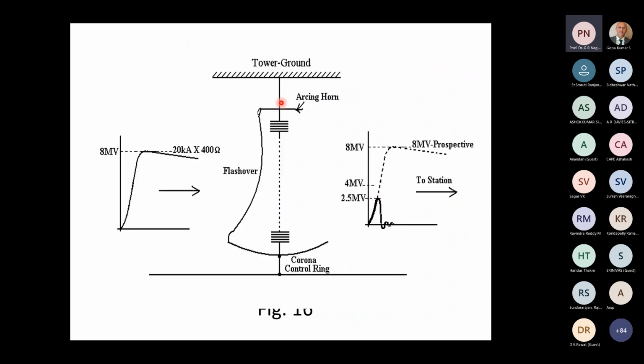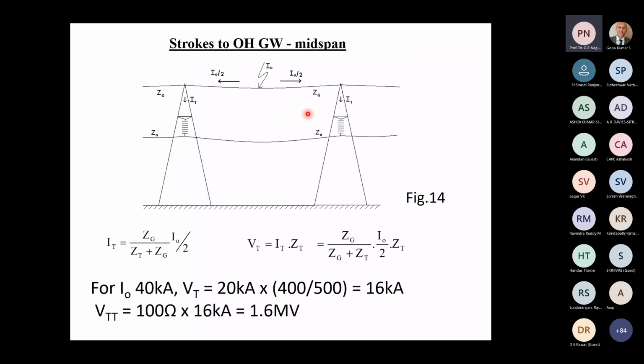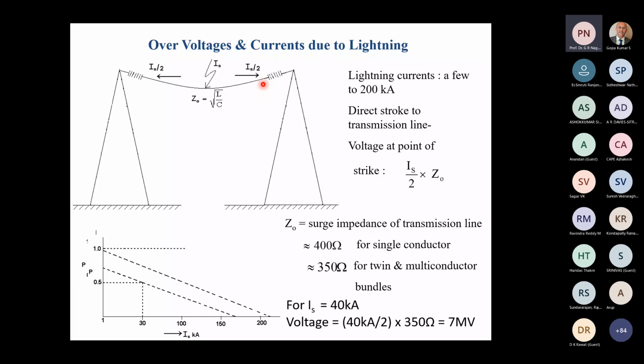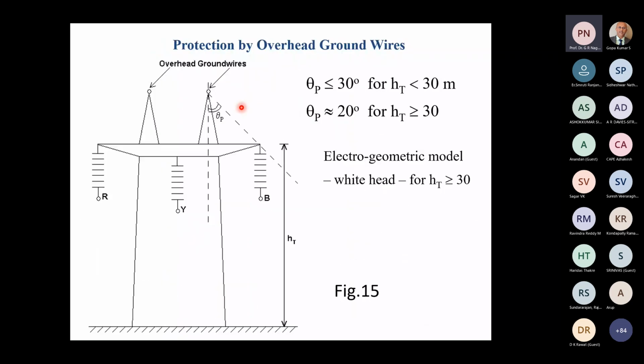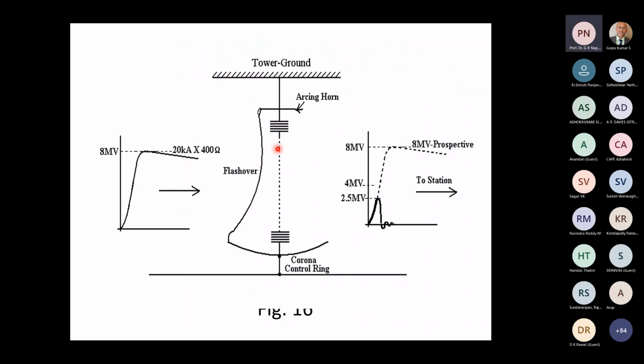Now, we have seen earlier that the voltage comes here to this point, travels here. This voltage appears across this insulator string. It can cause a flashover. If the voltage is high, it will possibly cause a flashover. So now, see now, the insulator string flashover. The flashover is typically occurring between what's called the corona control ring at the line end and the arcing horn at the ground end. This flashover.